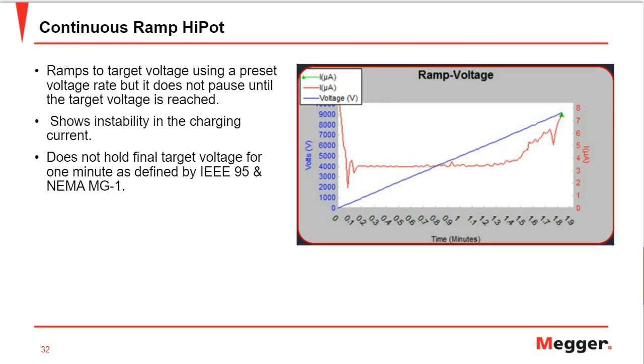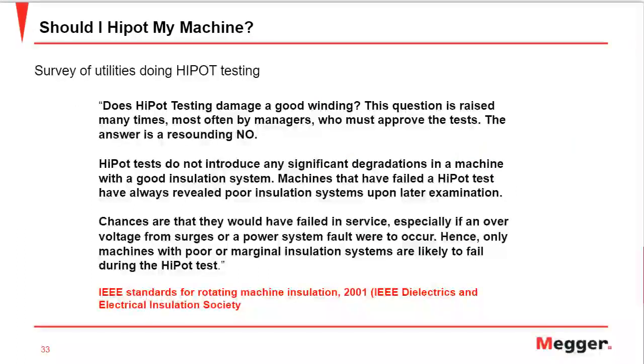So the question arises now: should we do hipot testing on our motors? Hypot testing is a conventional test. There are various standards that determine why the test is non-destructive. This is one of the articles from the IEEE standard for rotating machine insulation, 2001. It clearly states that if a motor has failed hipot testing, it is because it has some insulation degradation happening inside the motor. That's the only reason why a motor would fail a hipot test.